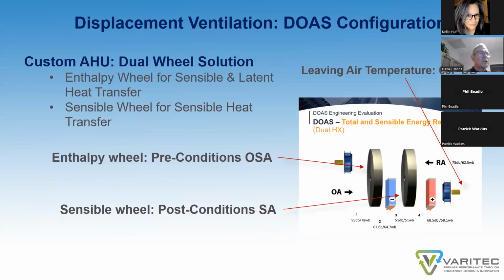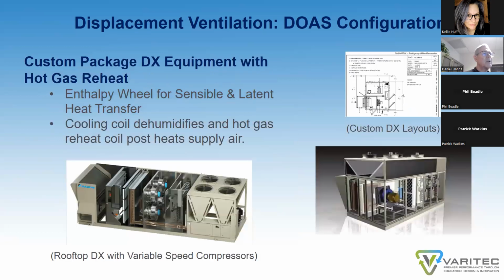Another option is to use a dual wheel 100% outside air unit, one that uses an enthalpy wheel to precondition the outside air both for sensible and latent heat. That preconditioned air then passes through the cooling coil, and there's a secondary sensible only heat wheel that transfers the energy from the room into the supply air stream to add another 5 to 10 degrees of temperature to the air coming off the coil, so we can supply 62 to 65 degrees of air that is properly dehumidified.